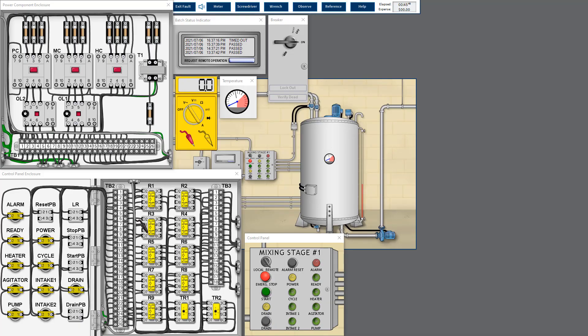Switch to AC voltage mode, then put the black probe at the ground point and measure the upstream of the fuse. There's a voltage — that means the upstream is okay. Then measure the downstream of the fuse — zero volts, which means the fuse is blown.